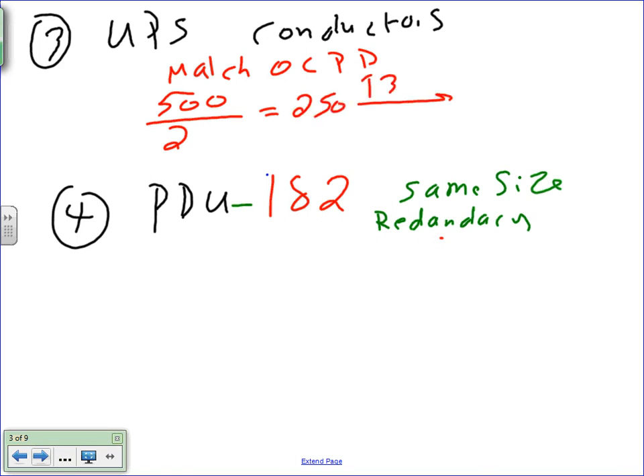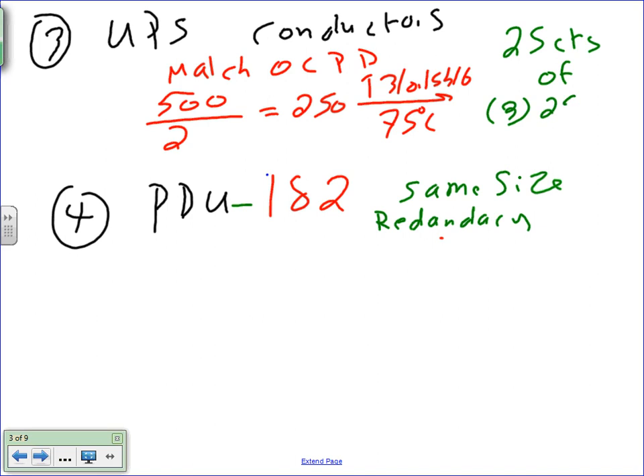Take this to table 310.15(B)(16) under the 75-degree column, and that will get me the following. That'll give me two sets of how many conductors? Now coming into the switchgear, I don't need a neutral, so 3 conductors of 250 kcmil. This is one way of sizing it. May I pull a conductor of 500 kcmil? You can. As I said, after you go higher than 400 amp, it's a good idea to start paralleling. Remember that cutoff, 500 kcmil or 400 amp? It's a good cutoff to do sizing.